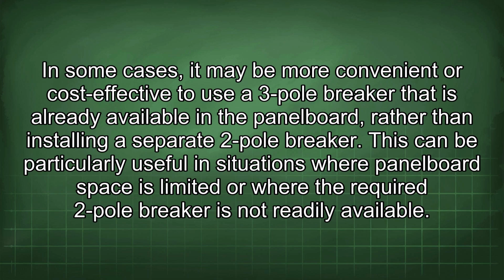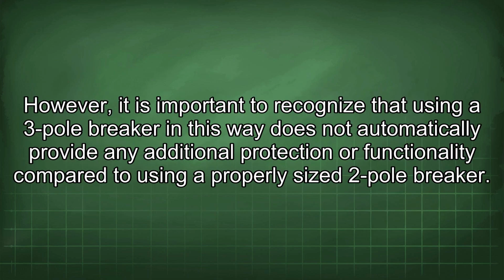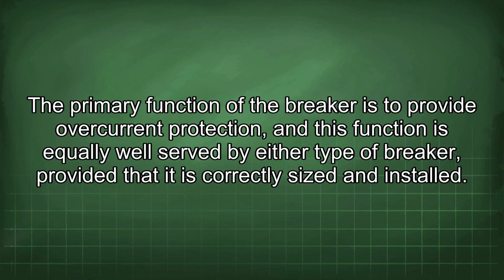not readily available. However, it is important to recognize that using a 3-pole breaker in this way does not automatically provide any additional protection or functionality compared to using a properly sized 2-pole breaker. The primary function of the breaker is to provide overcurrent protection, and this function is equally well served by either type of breaker, provided that it is correctly sized and installed.